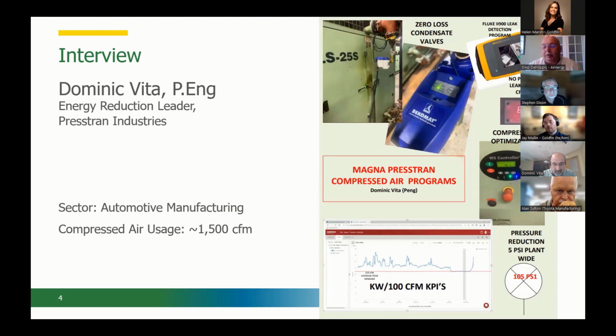It would be, I'll be honest with you, the savings, if he's using a variable to trim on a fixed speed compressor, I would have to look at what power charts you have so far. But if you're running the fixed speed at full load and the VFD is only trimming, controlling that would only allow you to optimize switching compressors 1 and 2, the fixed speed with the VFD still, and allow you to possibly use the VFD only on the weekend. But the compressor gap between ranges would still be a tight 5 to 7 PSI. So calculating the energy reduction with a controller, I would say there's probably not a lot of savings.